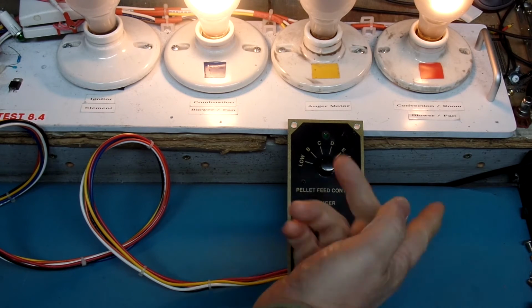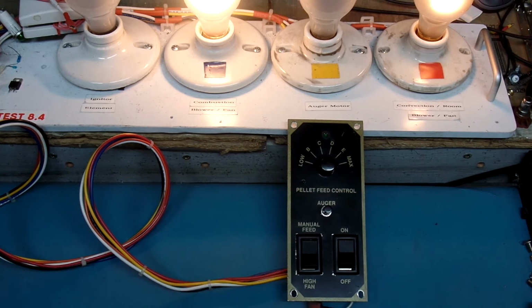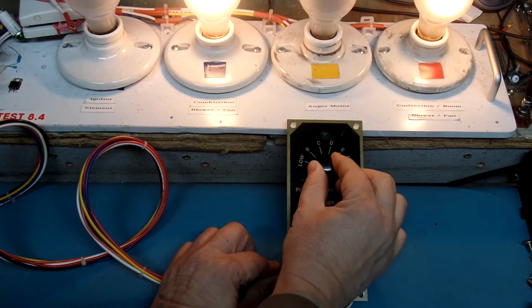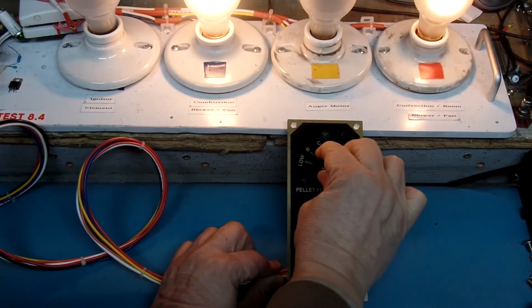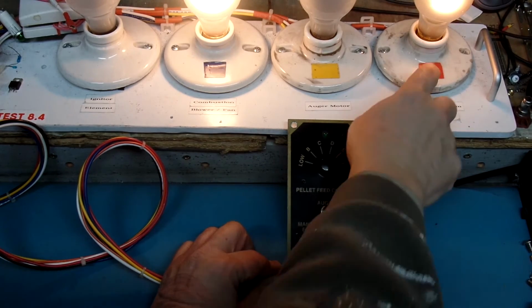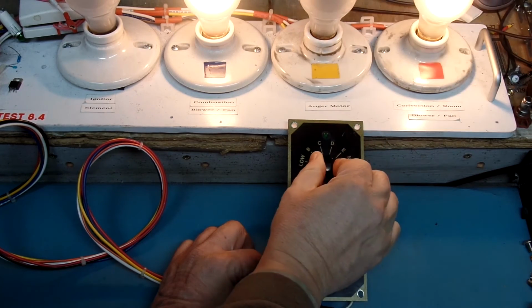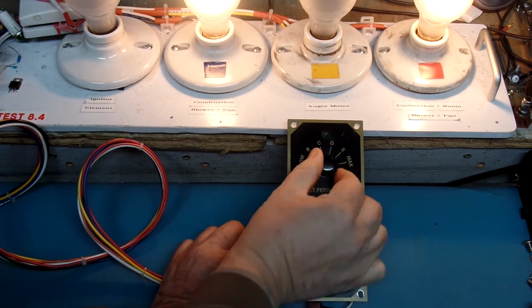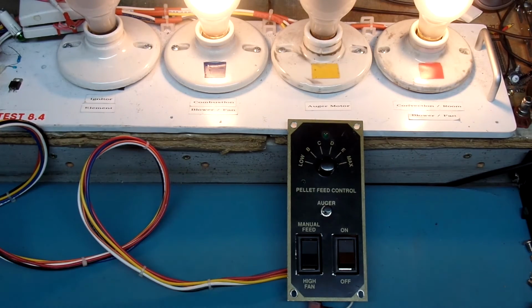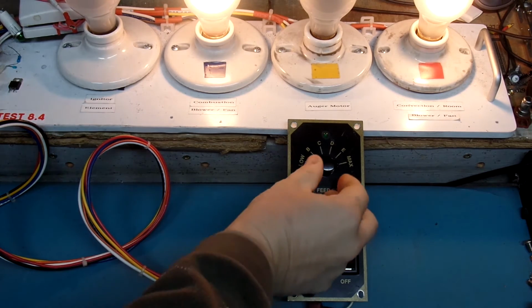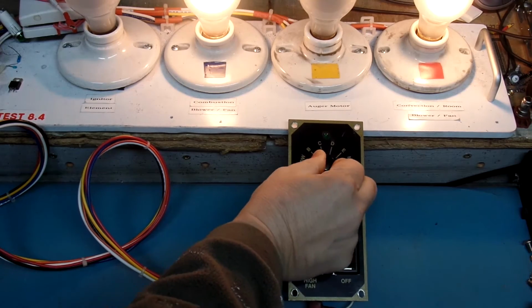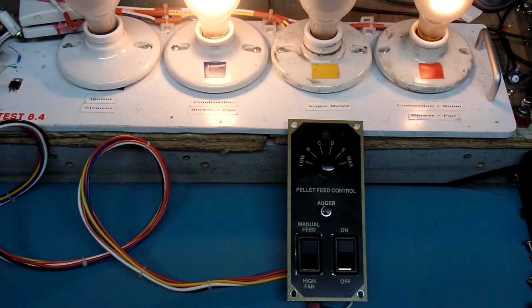So the other thing with it off, I can go through the low, B, C, D, E, and max positions on the controller. As we rotate through positions, we see the intensity of the convection room fan go up and down. Now I will note that D, E, and max have the same effect on the room fan. So they don't make it go faster or slower. That is hardwired in the controller and cannot be changed, but that is correct. D, E, and max are all the same, but C, B, and low are different. So those are the manual settings that we can check.